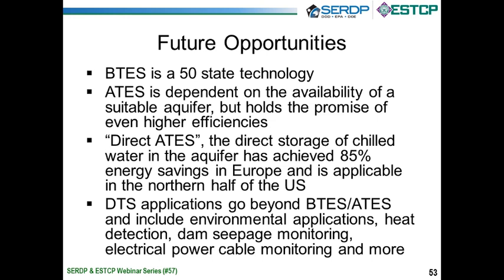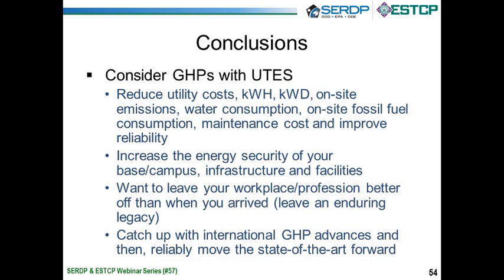And direct ATES, the holy grail, where we store chilled water directly in the ground, maybe in the northern third of the U.S., and we don't even run the compressor during the cooling mode, only running the compressors in the winter for heat, allows us a potential reduction of maybe 85%. So we think that's a great future opportunity, and I certainly think DTS has a lot of applications in the U.S. that it's not even being considered for. So in the end, if you want to achieve these goals that you see here in blue, including some professional goals, we would encourage you to consider one of these more state-of-the-art systems.